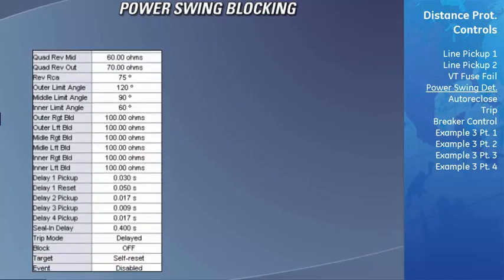The coordination timers need to be set to indicate how long the impedance needs to be in each zone in order for the D60 to block operation of the distance elements. Careful consideration needs to be taken to make sure that the fastest possible power swings will be detected. The power swing pickup delay timer 1 defines the time that the impedance must spend between the outer and inner characteristics in the 2-step operating mode before the power swing blocking signal is established. This time delay must be set shorter than the time period required for the impedance locus to travel between the 2 selected characteristics during the fastest expected stable power swing.